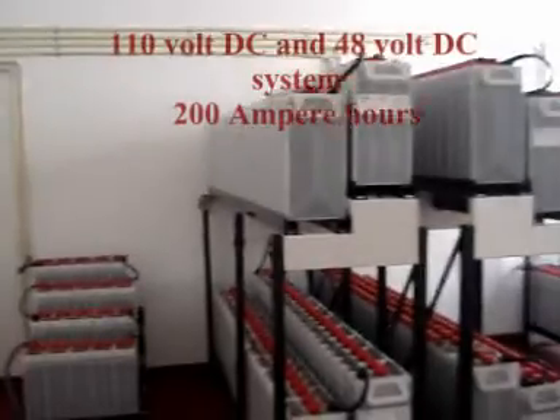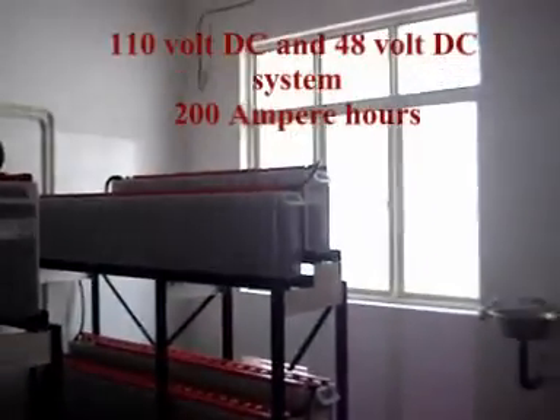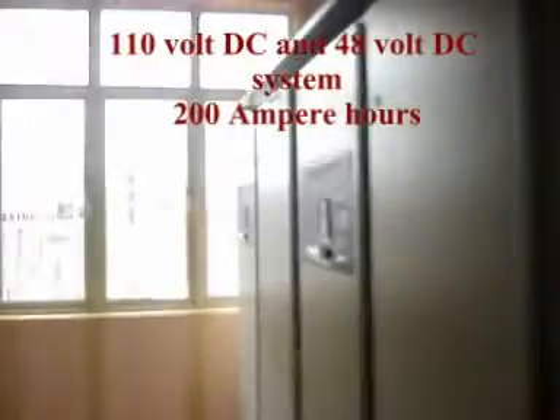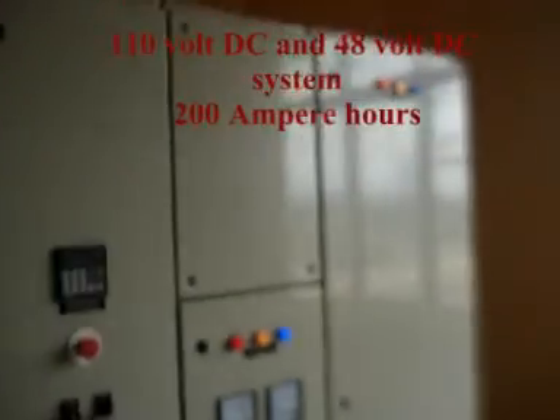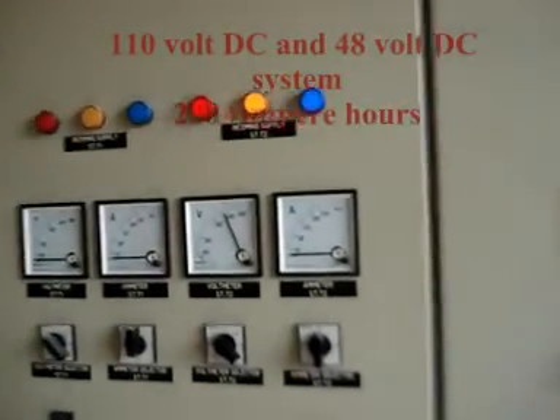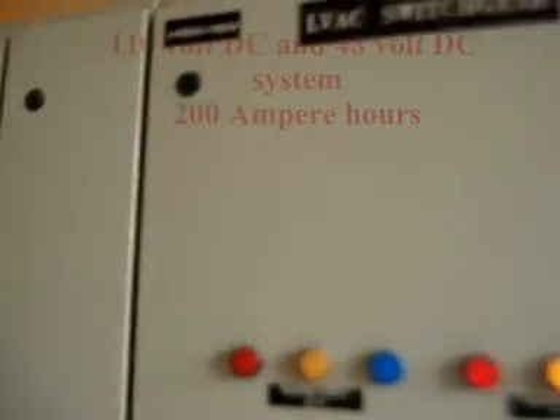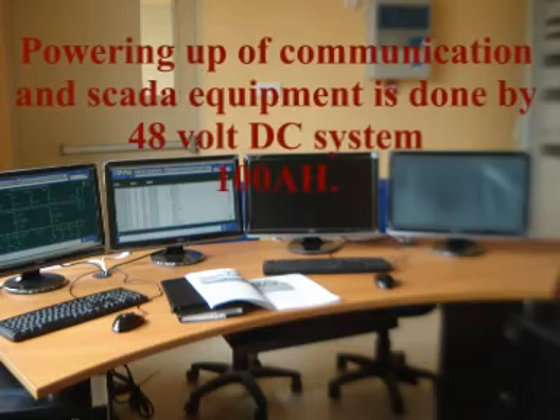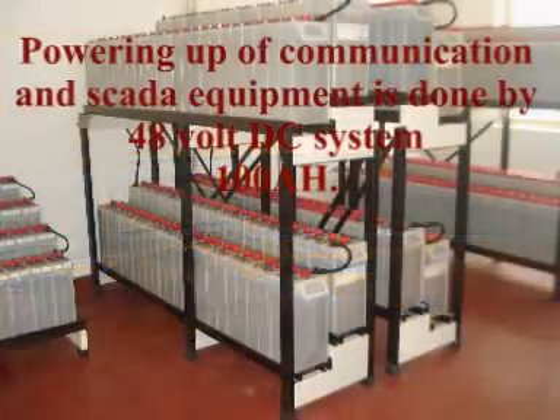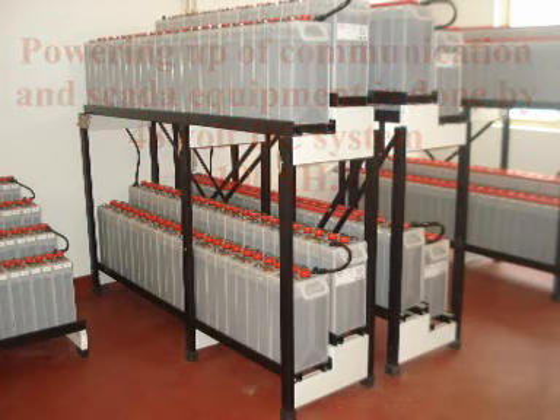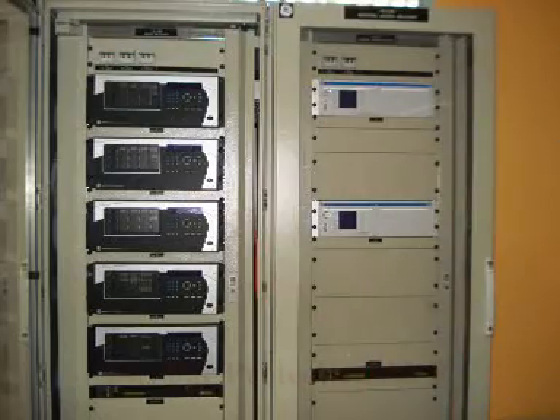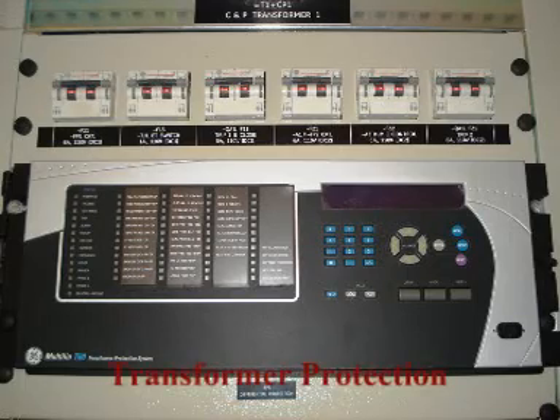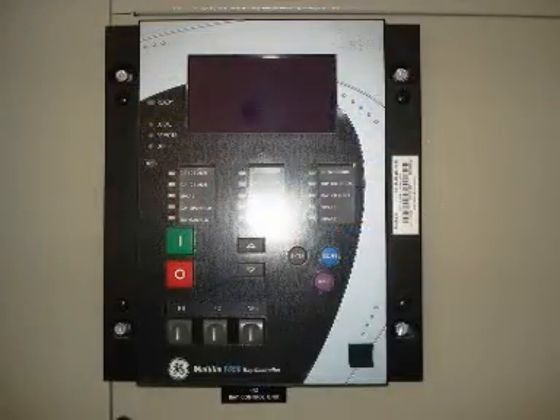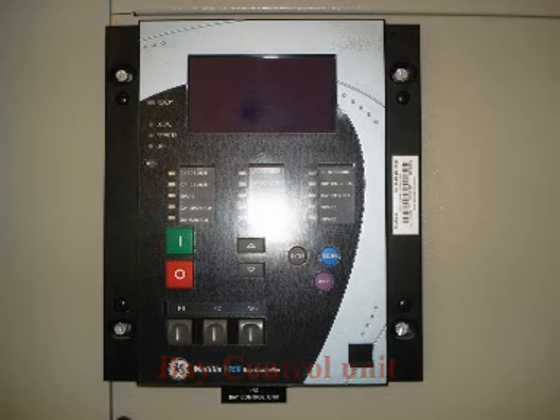This substation has storage battery systems in both 110 volt DC and 48 volt DC. The 110 volt DC system is used for switchgear tripping and closing duties, alarms and indications, and emergency lighting. The rating is higher than 200 ampere hours. Powering of communication and SCADA equipment is done by the 48 volt DC system, which has a capacity of 100 ampere hours. Control and protection functions for all equipment are provided through GE relays manufactured in Canada. Such relays are wired and assembled in control and relay panels manufactured by GE India.